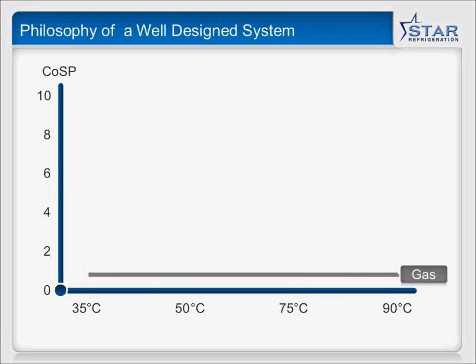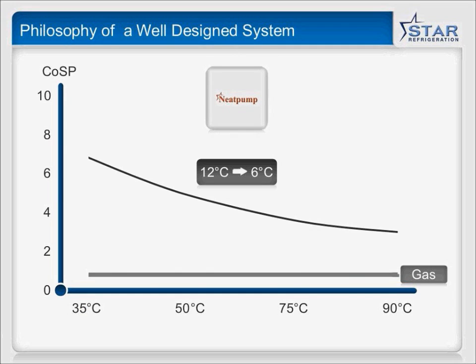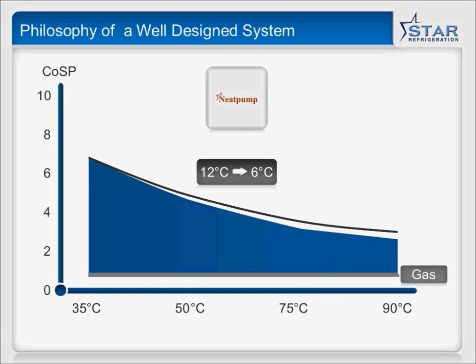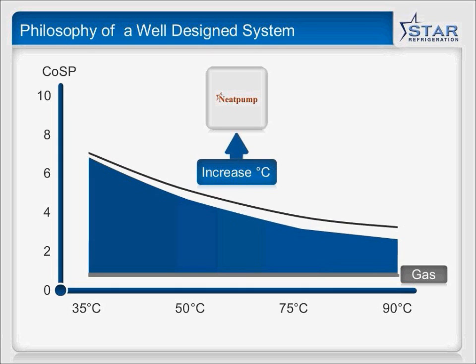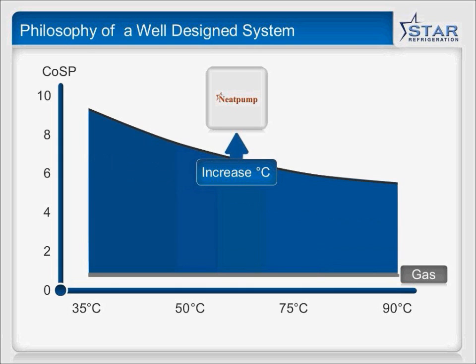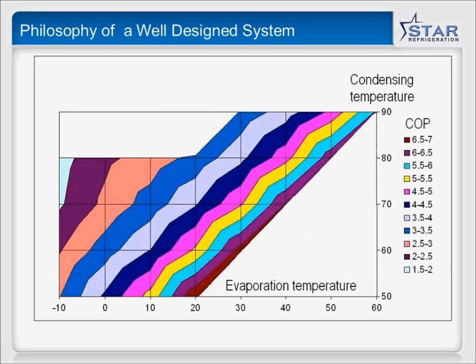However, sometimes we can be doing things like data centres, cooling them at 20 degrees and delivering the heat at 60 degrees. We could have a COP of 5 just for the heating part. So getting the temperatures right matters, and generally we want to move in the direction of the arrow to push the COP higher.